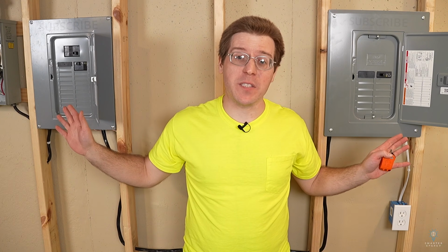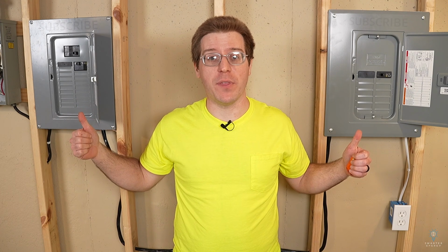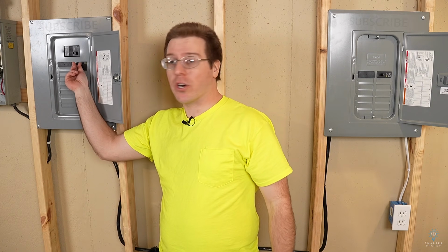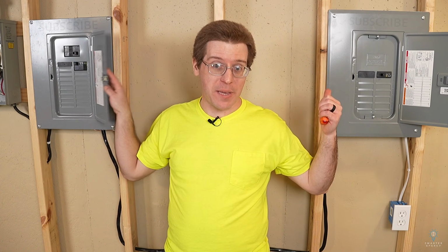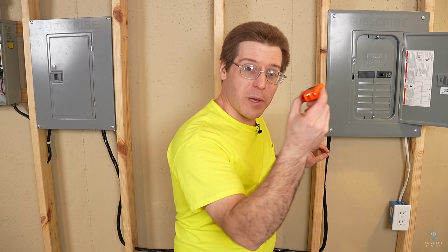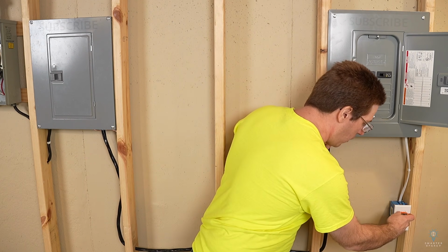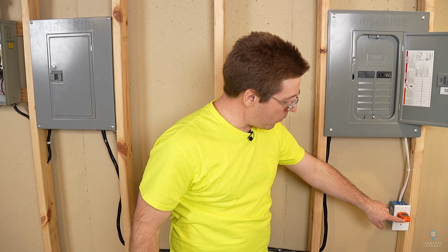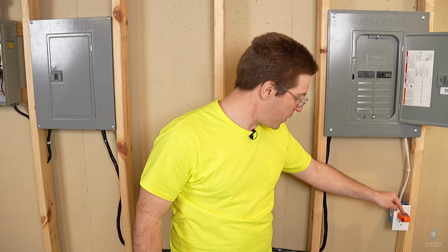So with that, everything is buttoned up. We should be safe to fire everything up. So let's go ahead and turn on the sub panel. So the sub panel is now energized. And we can plug our outlet tester into our outlet and flip our circuit on, and we get 2 orange lights, which with this tester means the receptacle is wired correctly.